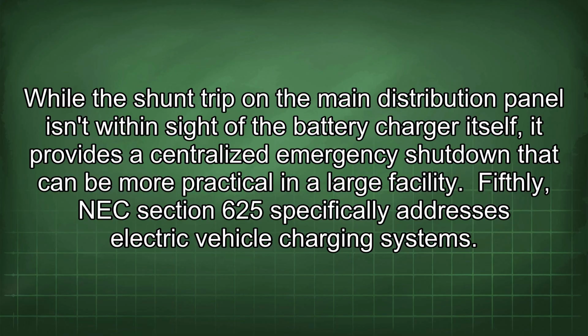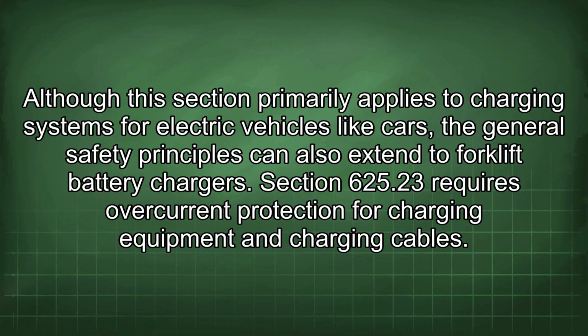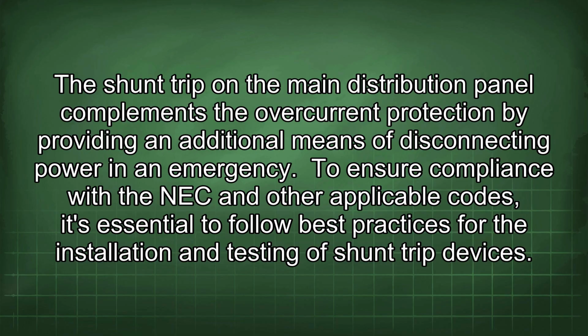Fifthly, NEC Section 625 specifically addresses electric vehicle charging systems. Although this section primarily applies to charging systems for electric vehicles like cars, the general safety principles can also extend to forklift battery chargers. Section 625.23 requires overcurrent protection for charging equipment and charging cables. The shunt trip on the main distribution panel complements the overcurrent protection by providing an additional means of disconnecting power in an emergency.